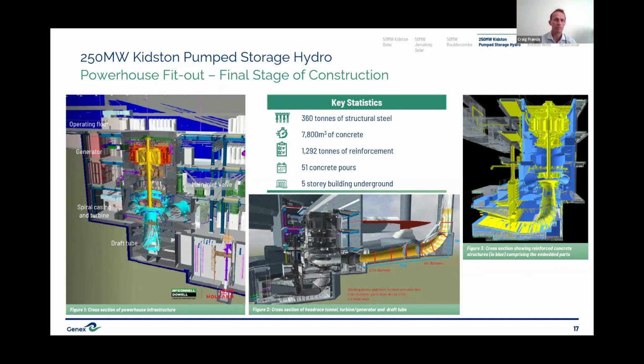You can see in the image on the left a cross-section of the underground power station, essentially a 5-story building underground comprised of 5 levels. The draft tube level is where water drops from the pump turbine down through to the tail race tunnel - you can see a cross-section of that on the far right in blue, the draft tube being the lower yellow piece. That big vertical gate is the draft tube gate, which stops the flow of water in and out of the draft tube.